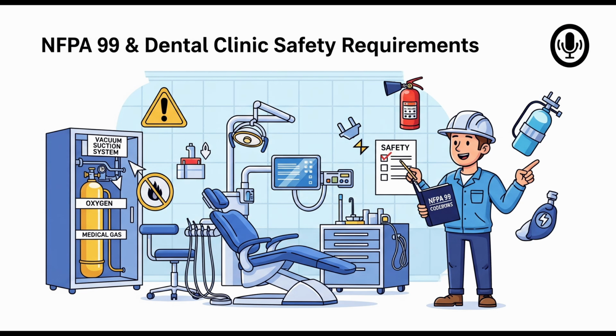Okay, good to know. And like the gas systems, I assume electrical systems need maintenance. Absolutely. Section 6.9 mandates a documented preventative maintenance program. This includes regularly testing things like circuit breakers and the batteries for any backup power systems. And just like with gas, Section 6.9.2 requires keeping detailed records of all electrical testing and maintenance. Documentation is key for proving ongoing compliance. Right, you need that paper trail.